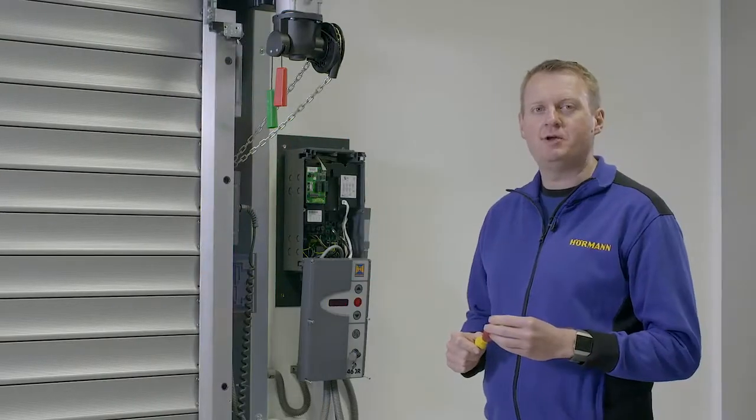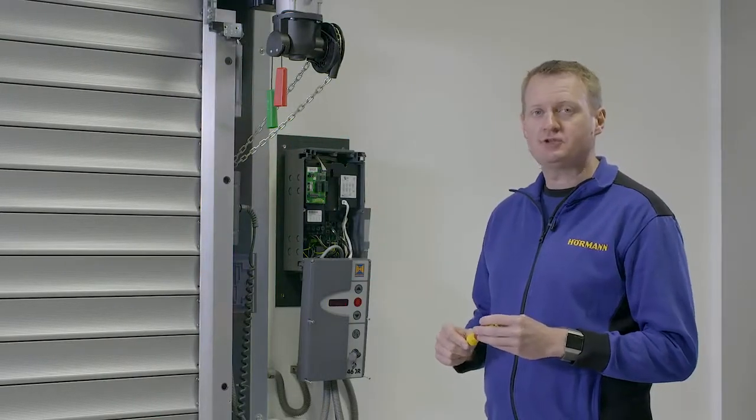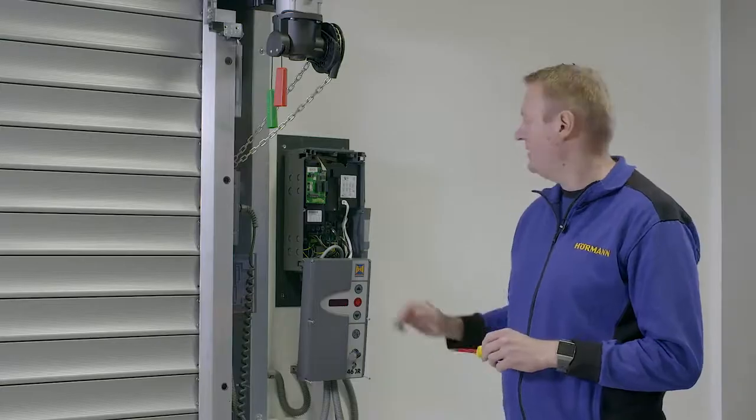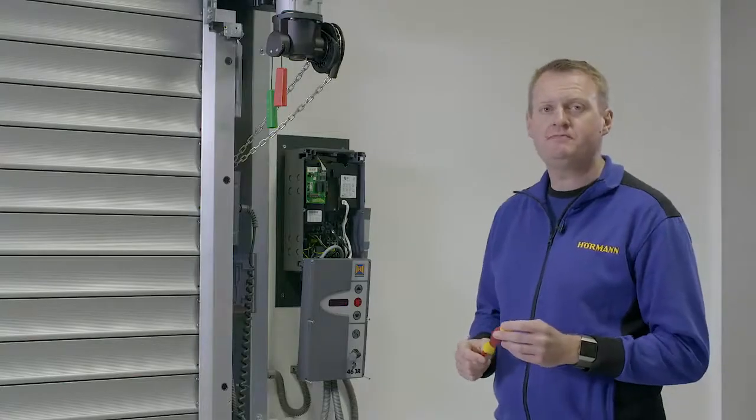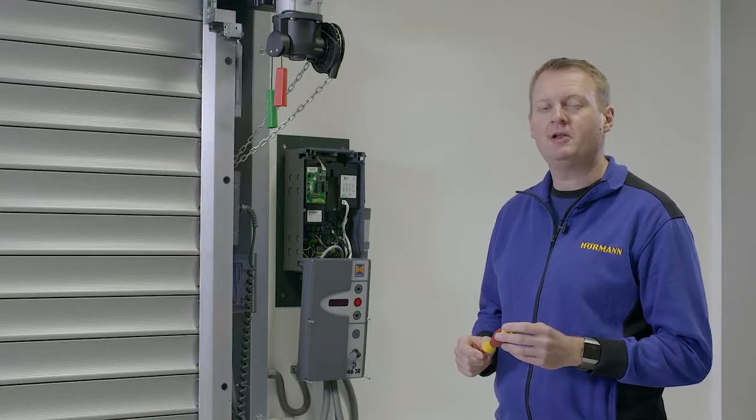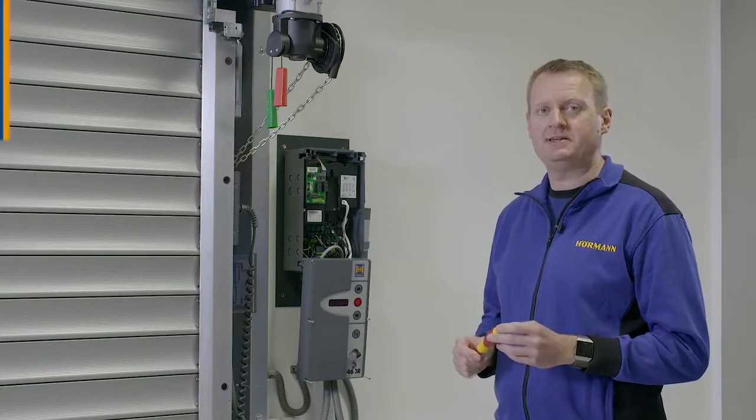A common fault code is 01. This is a 24 volt stop circuit wired into either terminal x1, x3, or plugged into x10. This could be either an emergency stop button, an interlock from another system like an airlock, or an anti-fall device if fitted.